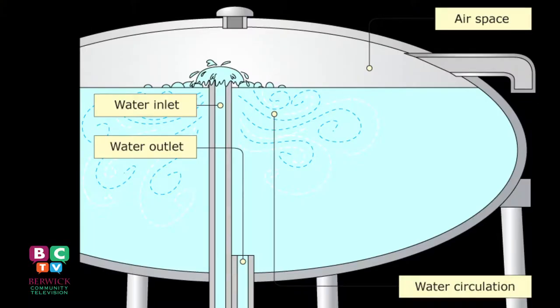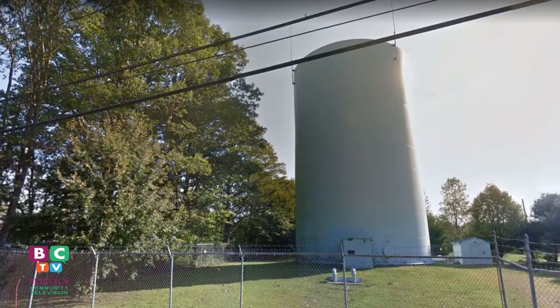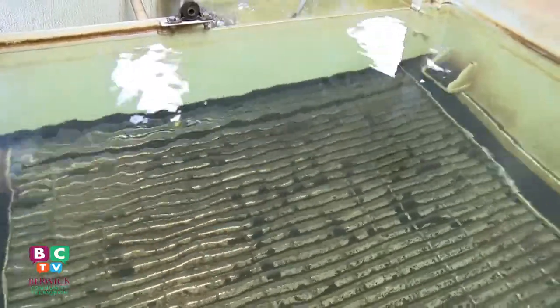The things we'd like to do — we'd like to have a circulation system in the water tank up on Pine Hill. It's a blue-green tank alongside Pine Hill Road heading northwest, with 1.1 million gallons in it. That's where we store the water we make, so that if the plant isn't running, everybody still has water. The town is fed by gravity when the plant is off. On slow winter days the plant runs six or seven hours; in the summer, sometimes up to 12, 14, or 16 hours. We're lucky we don't have to run 24 hours a day.